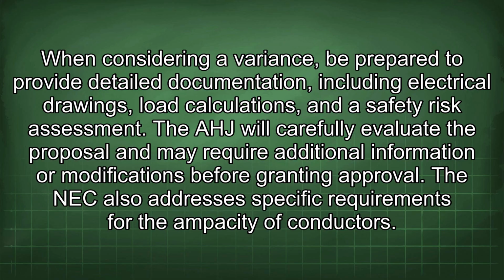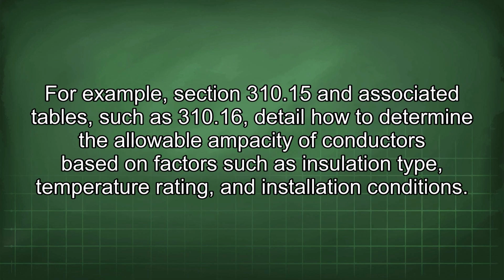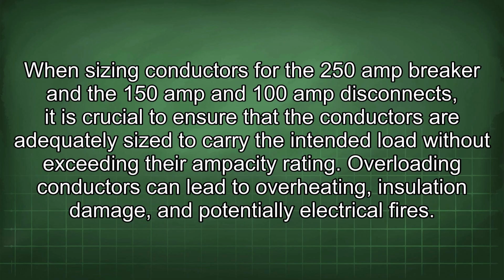The NEC also addresses specific requirements for the ampacity of conductors. For example, Section 310.15 and associated tables such as 310.16 detail how to determine the allowable ampacity of conductors based on factors such as insulation type, temperature rating, and installation conditions. When sizing conductors for the 250 amp breaker and the 150 amp and 100 amp disconnects, it is crucial to ensure that the conductors are adequately sized to carry the intended load without exceeding their ampacity rating. Overloading conductors can lead to overheating, insulation damage, and potentially electrical fires.